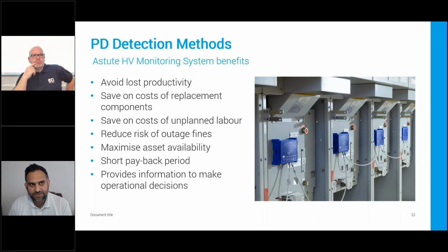services. And the idea with the Astute monitoring service is that instead of you nominating specific engineers within the company looking at the data 24/7 or whenever the alarms occur, you can actually get PD experts like EA Technology to look at those assets for you, and then we can look at the alarms, and we can make the first pass and make the judgment whether the activity that we're picking up is genuine partial discharge activity or whether it's just external noise that we're picking up. So you can focus on your day jobs while we look at the partial discharge activity for you, and you can make informed operational decisions based on what data we feed back to you guys.